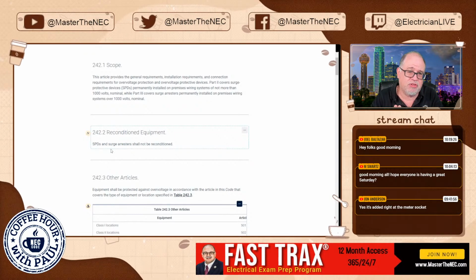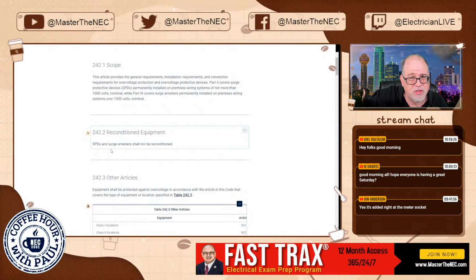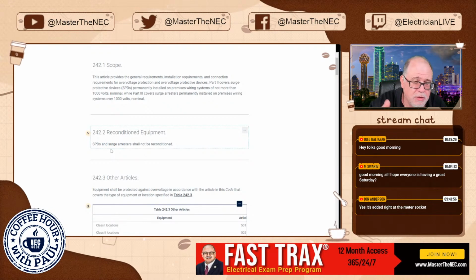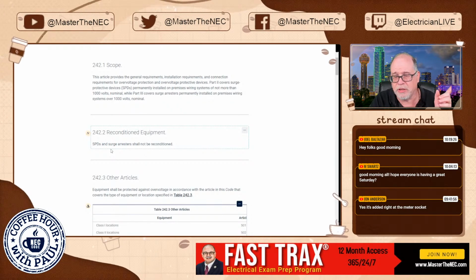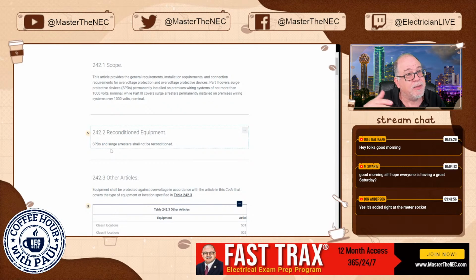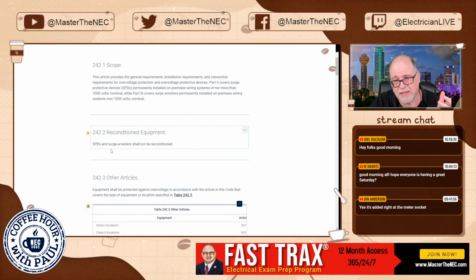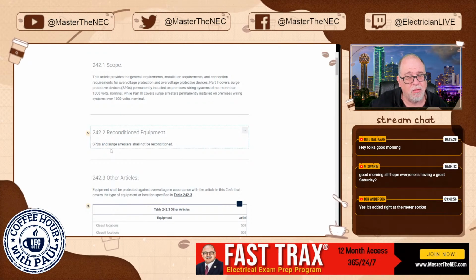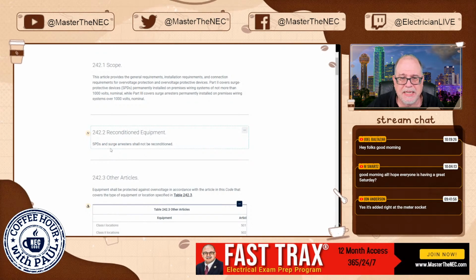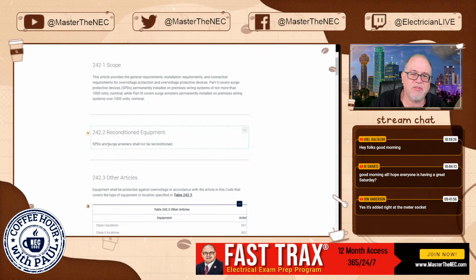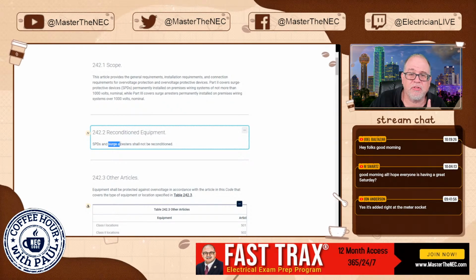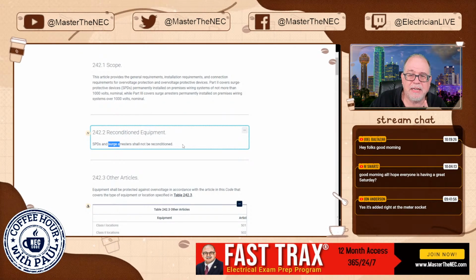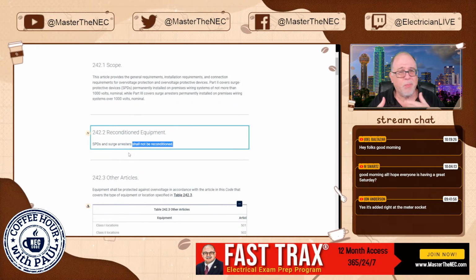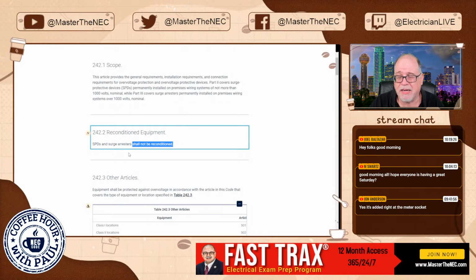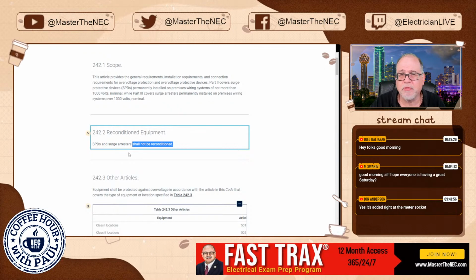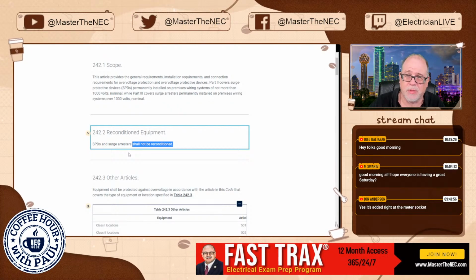It's been put in .2. So remember, .2 used to be definitions that were germane only to a specific article. Well, remember, those definitions are now in 100 in the 2023 edition. So that freed up .2. And as you saw previously for reconditioned equipment, now you see it also applies to SPDs. So surge protective devices and surge arresters shall not be reconditioned. So these are important devices, and they have a lot of electronics in them. We're not going to recondition them. You're just going to buy a new one, okay?